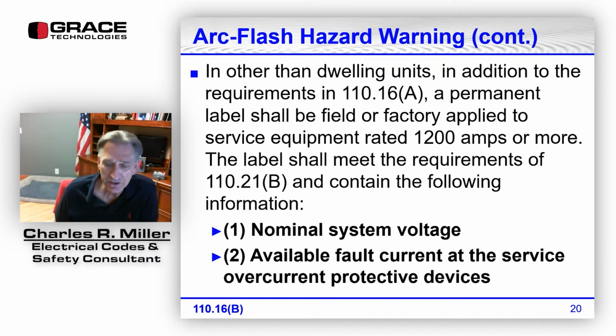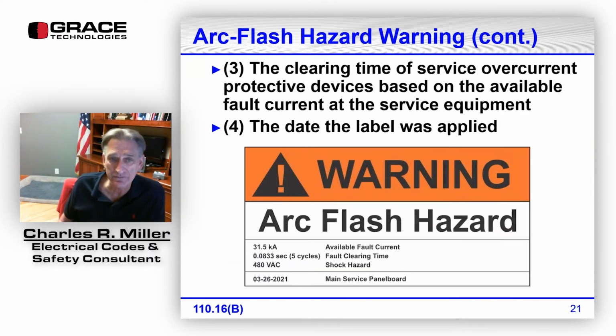All right, and for the B part, in other than dwelling units, in addition to the requirements in 110.16, a permanent label has to be field or factory applied to service equipment rated 1200 amps or more. This label has to meet the requirements of 110.21(B), which is a labeling and marking requirement, and has to contain certain information. So this is required for service equipment, but only the larger service equipment rated 1200 amps or more. What does the label have to contain? It has to contain the nominal system voltage, available fault current at the service overcurrent protective devices, and number three, the clearing time of the service overcurrent device based on the available fault current at the service equipment, and the date the label was applied.